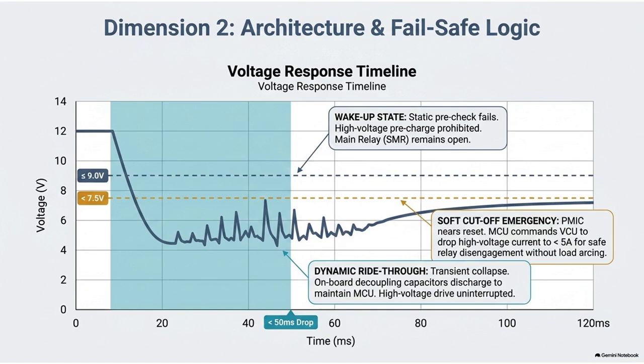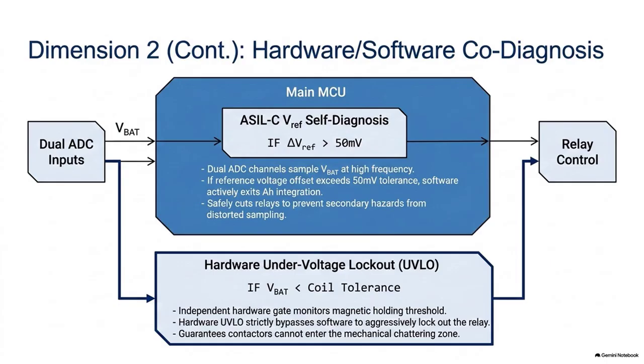Exactly. The UVLO is an analog hardware comparator circuit that monitors the coil drive voltage completely independently of the microcontroller. It has a hard-coded threshold, usually around 7.5 to 8 volts. The absolute millisecond the voltage drops to that threshold, the hardware comparator flips. It doesn't wait for the MCU. No, it forcefully and mechanically severs the drive signal to the contactor coil, utterly bypassing any software control. It just violently pulls the plug on the electromagnet, allowing the heavy springs to snap the contactor completely and cleanly open before it can enter that jittering arc zone. It demands a binary state, right?